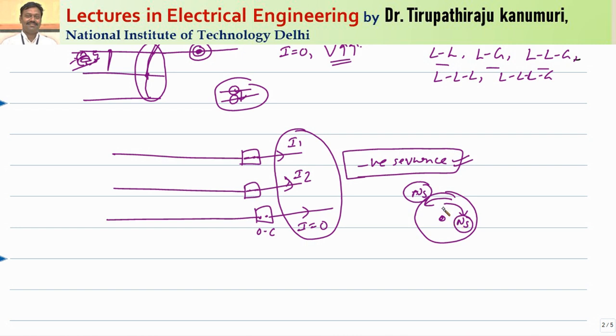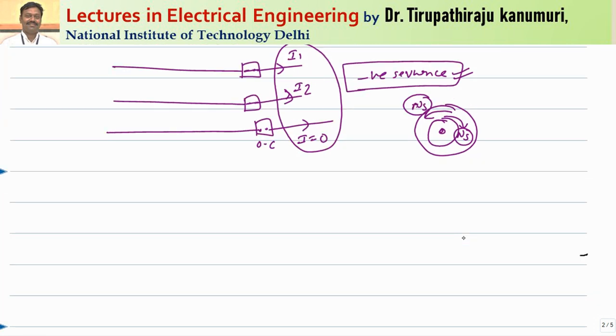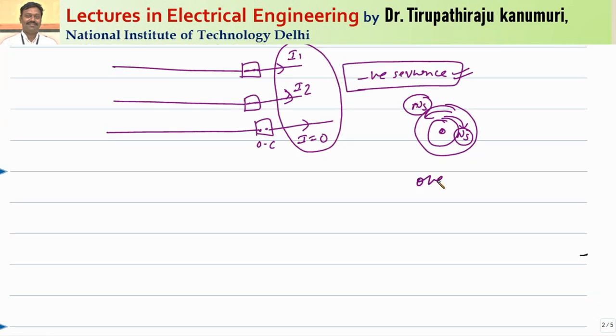These huge voltages lead to huge circulating currents and damage the rotor. These things will be discussed in detail in the fault analysis section when discussing sequence components. This was also discussed in the harmonics of machines and the damper winding concept — how negative sequence components lead to increased voltage values, causing complete imbalance in the system and overheating of machines.